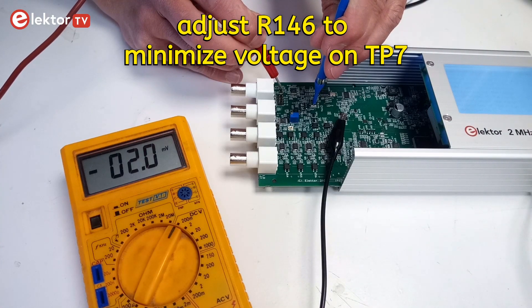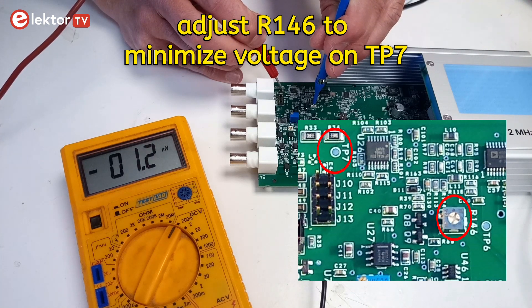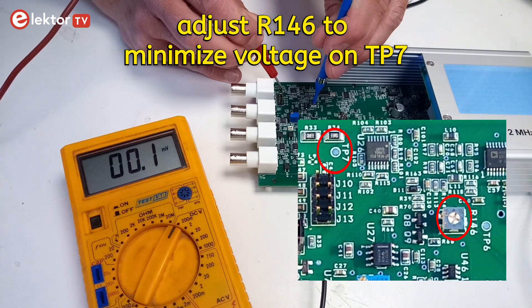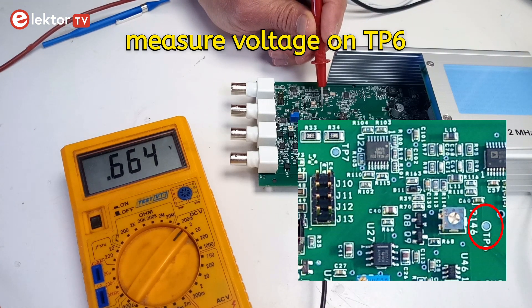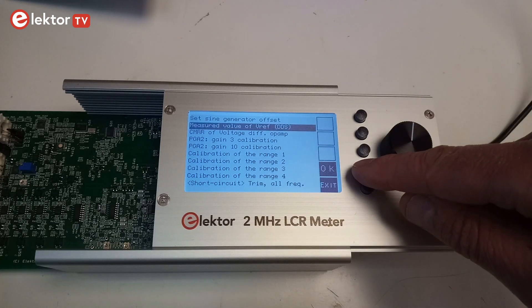Select sine wave generator offset adjustment. Using a voltmeter, adjust R146 to minimize the voltage on TP7. Then measure the voltage on TP6 and enter it using the rotary encoder. Select measured value of Vref.